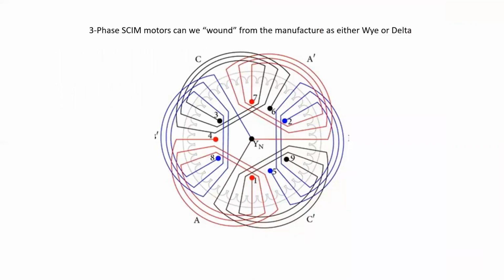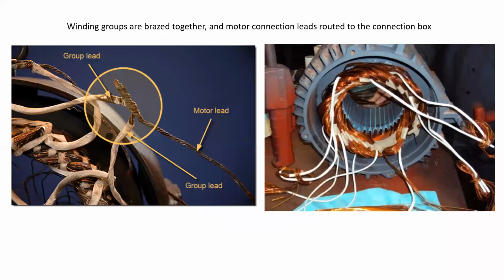Now, three-phase squirrel cage motors can be wound from the manufacturer as either Y or delta. Now, this particular image that I'm showing here, it's not important that you memorize or even sketch it. Rather, I want you to see that there is a series of loops, which are the windings in the stator, and they're connected in such a way for this particular motor in a Y formation. Each of these little winding groups are then brazed together at the manufacturer, and the motor connection leads are routed to the connection box, which has all sorts of clever names in the field. That's what these wires are that we see on the side.